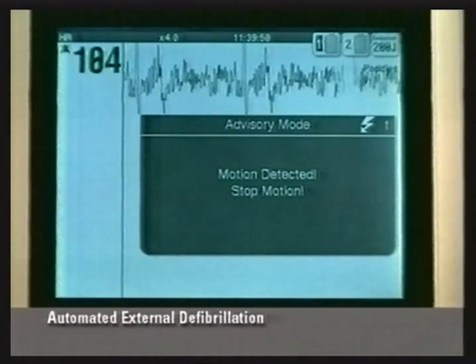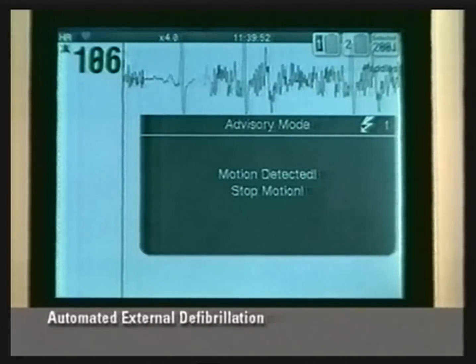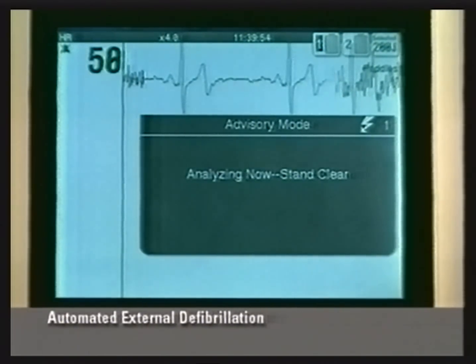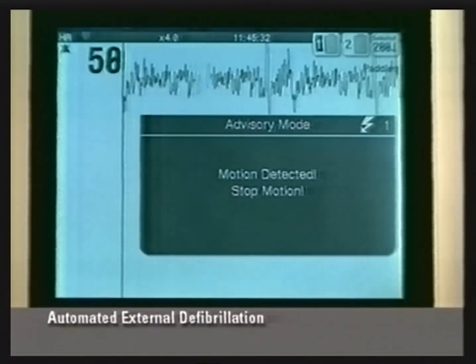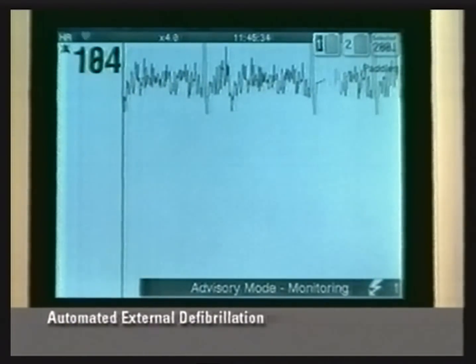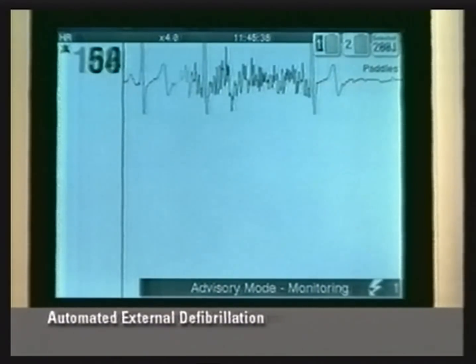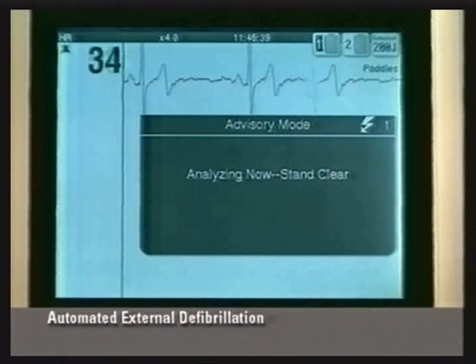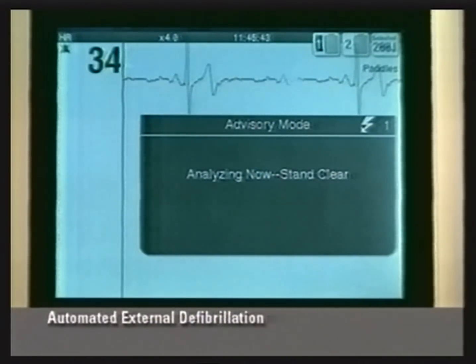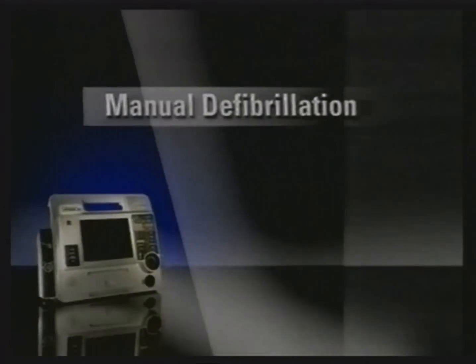If the motion detected message stops within 20 seconds, the defibrillator continues its rhythm analysis. Stand clear. If the motion detected message does not stop within 20 seconds, the defibrillator stops analyzing. You need to eliminate the motion and push the Analyze button again to restart analysis of the patient's ECG rhythm. No shock advised. This concludes the advisory or AED mode section of this video.